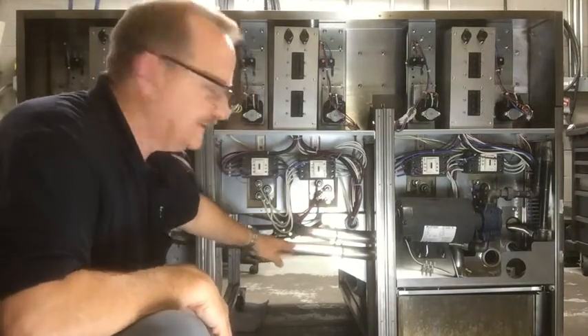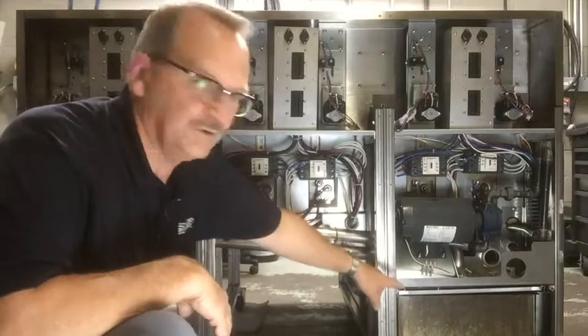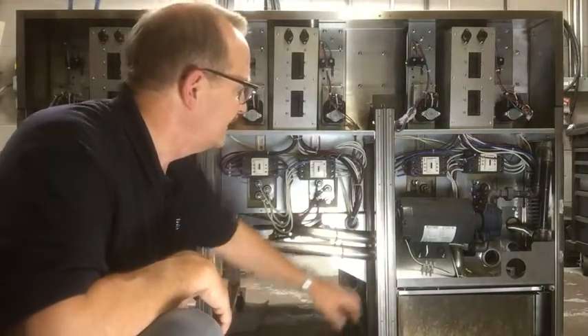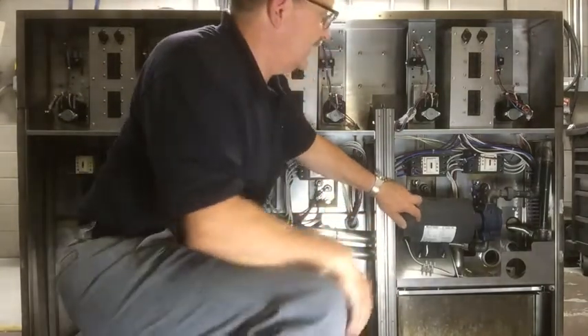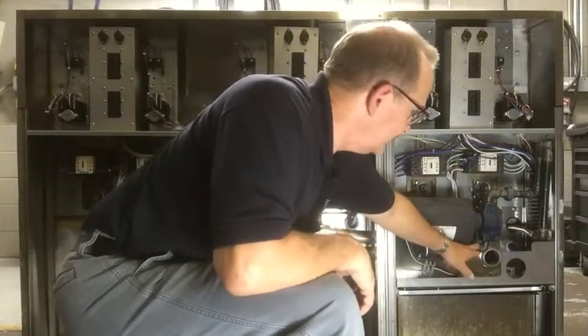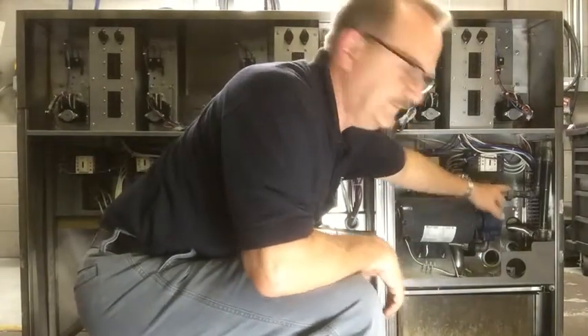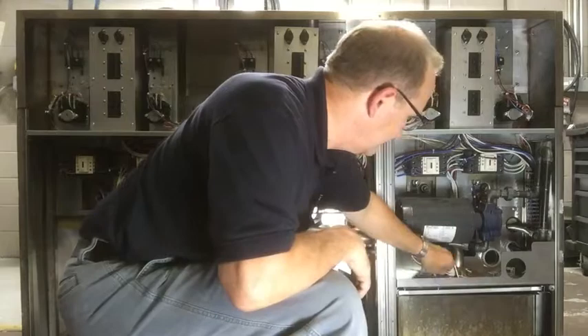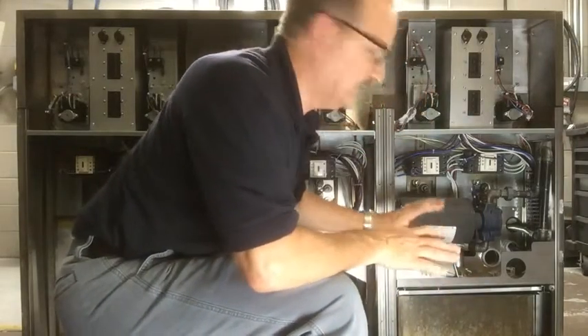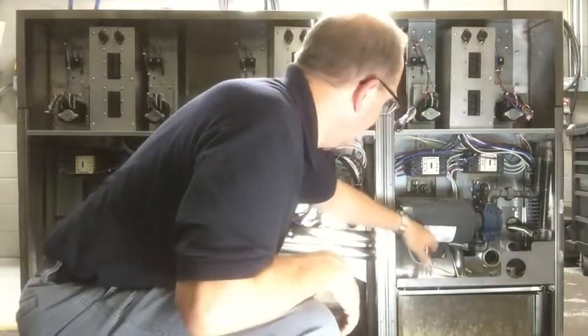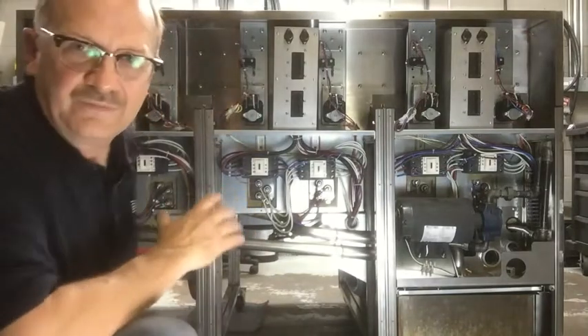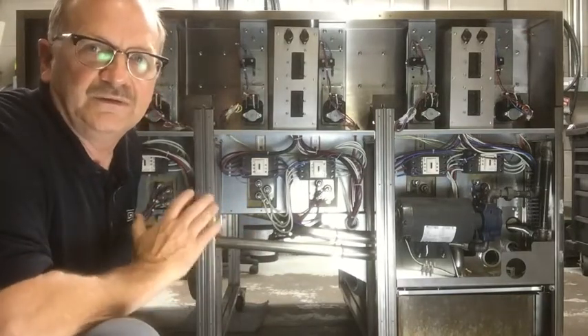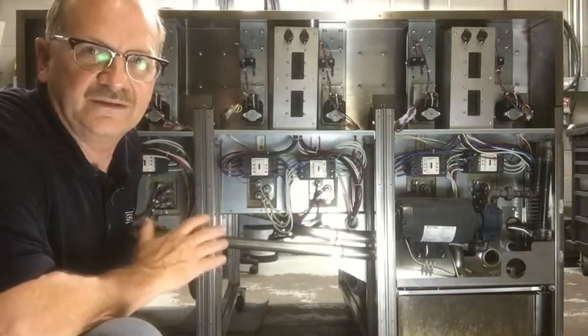These are the drain lines from each of the units. They all go to a central filter pump. The filter pump right here: outlet, inlet, break the union, take the hose loose, 2 wires, and the pump can be removed with 4 bolts. Everything is made to be simple, to make it easy to take care of and get it out of the way.